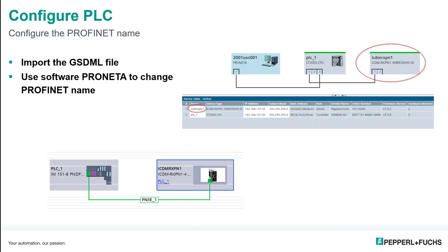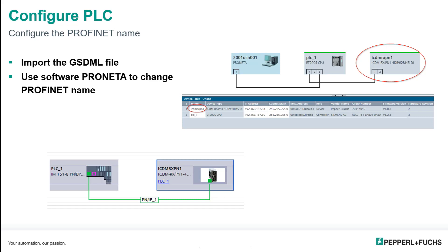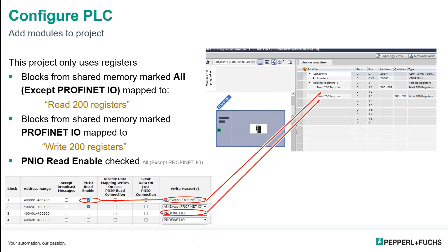Next thing, let's jump to the PLC. So we're going to add our PROFINET device, our DeviceMaster PN1 to the PLC software. And this is the TIA Portal software. But the first thing you want to do is import the GSDML file and use PRONETA or some other tool to set the PROFINET name. This is going to make it very easy for you in the next step when you add the device to the configuration.